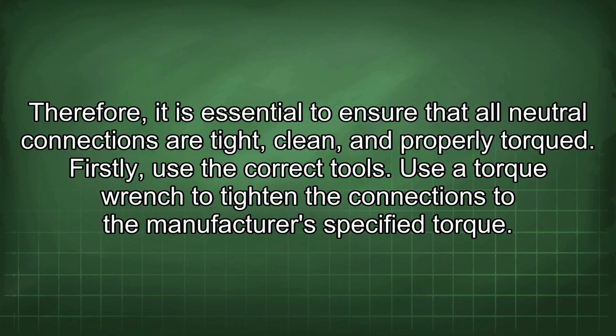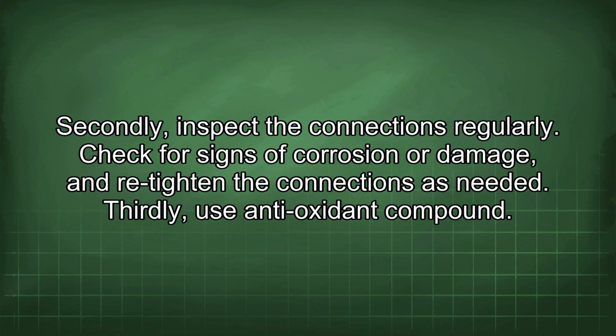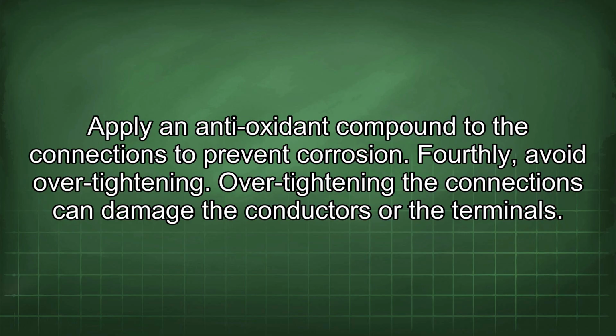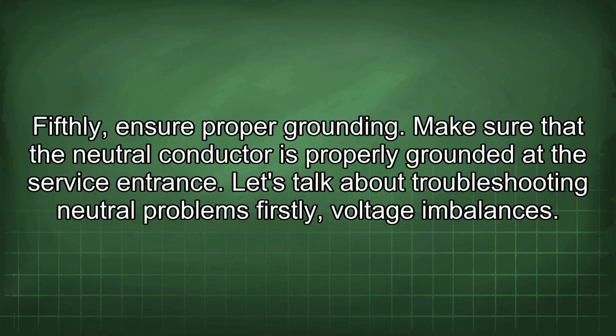Firstly, use the correct tools. Use a torque wrench to tighten the connections to the manufacturer's specified torque. Secondly, inspect the connections regularly. Check for signs of corrosion or damage, and retighten the connections as needed. Thirdly, use antioxidant compound. Apply an antioxidant compound to the connections to prevent corrosion. Fourthly, avoid over-tightening. Over-tightening the connections can damage the conductors or the terminals. Fifthly, ensure proper grounding. Make sure that the neutral conductor is properly grounded at the service entrance.